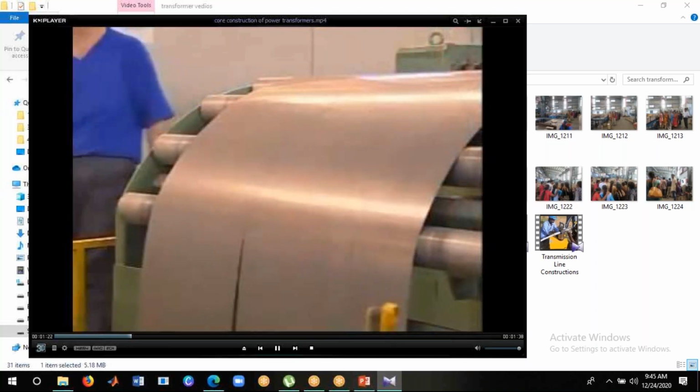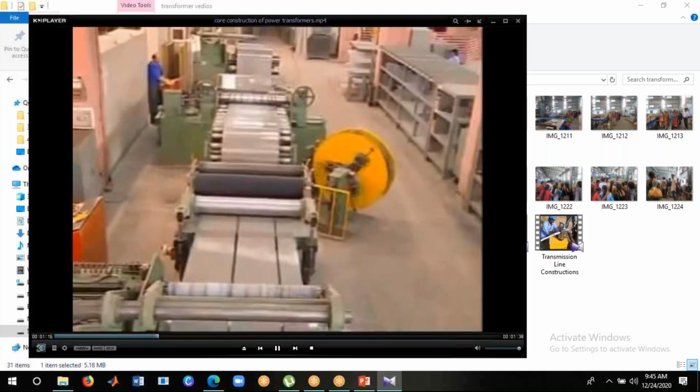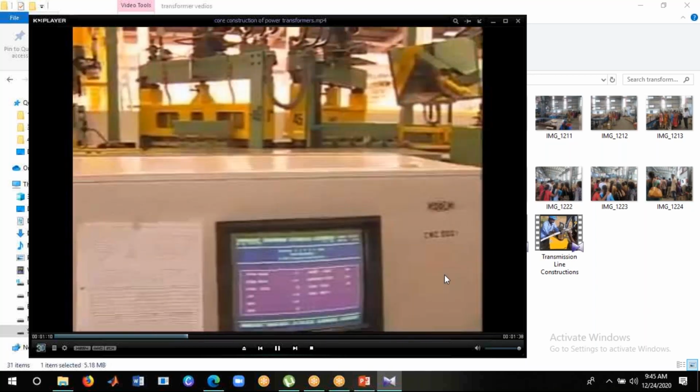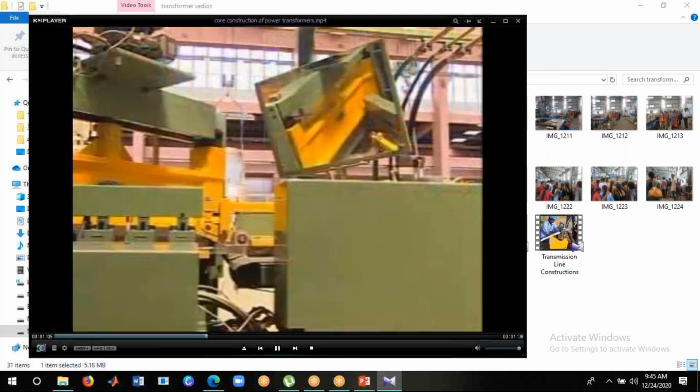Lower and upper yokes on a plate, core body is prepared. Both surfaces of metal sheets have Carlite insulation. In order to obtain smaller no-load losses and no-load current, highly permeable silicon steel sheets of suitable quality are processed in CNC-controlled machines.